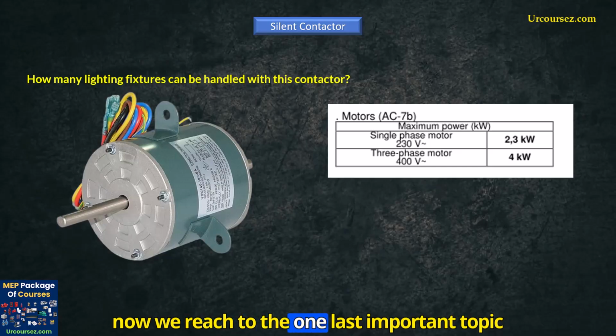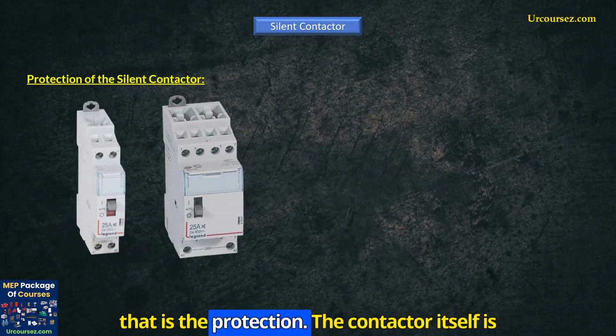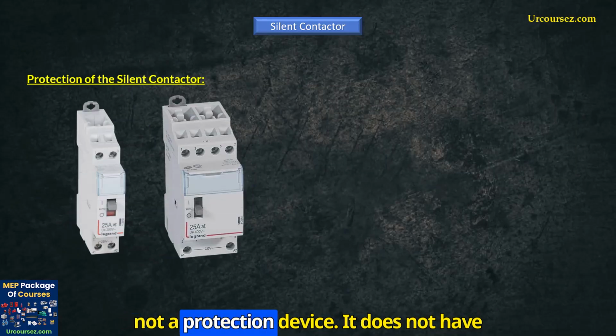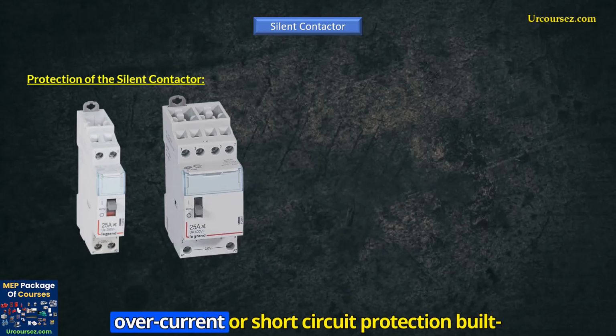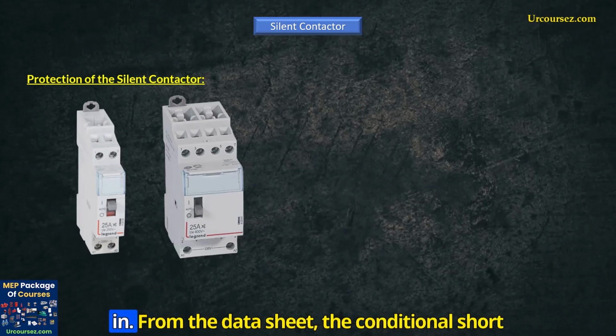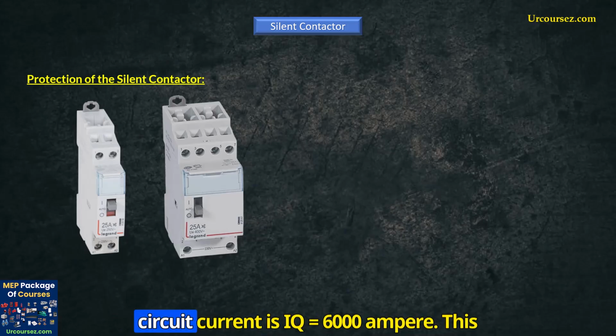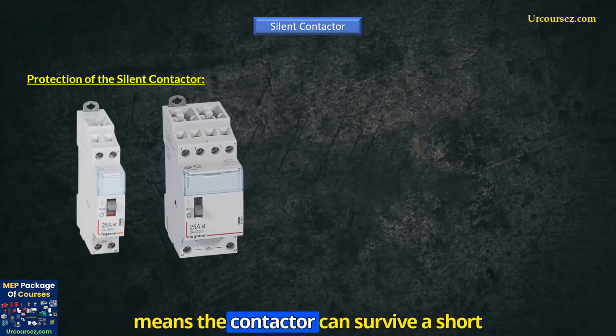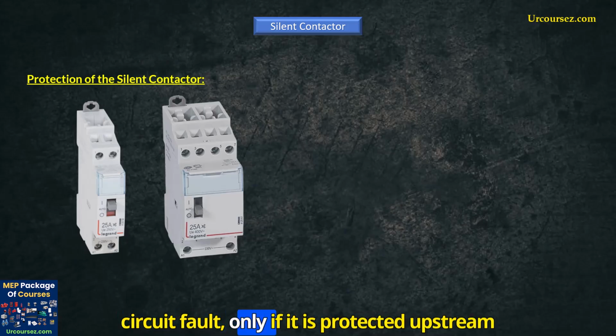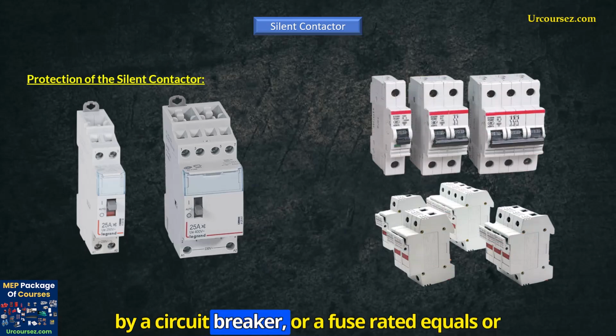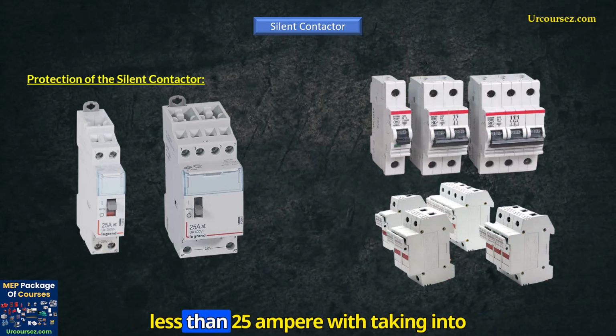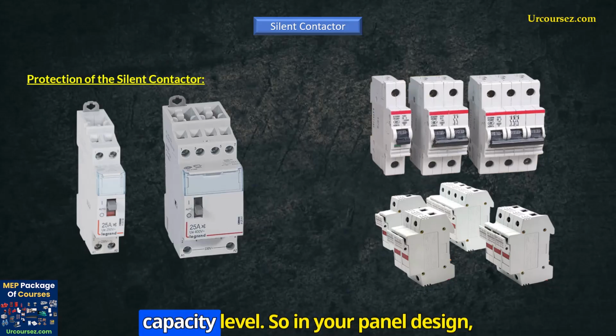Okay, now we reach the one last important topic, that is the protection. The contactor itself is not a protection device. It does not have overcurrent or short circuit protection built in. From the datasheet, the conditional short circuit current is IQ equals 6,000 amperes. This means the contactor can survive a short circuit fault only if it is protected upstream by a circuit breaker or a fuse rated equal to or less than 25 amperes, taking into consideration the suitable short circuit capacity level.